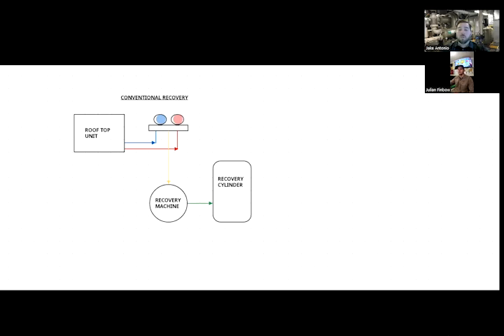And then again, you would want a weigh scale there to verify how much refrigerant was in your system and how much you pulled out, and you can verify that against the nameplate. Maybe you had a leak on your system and you want to see how much refrigerant you lost, then you can weigh it and compare it to the nameplate. And then when you're done with the repair, you can put the gas back in and add some more if you need to get it back up to the factory charge. So that's the conventional recovery method there.